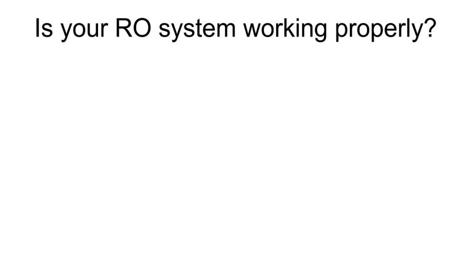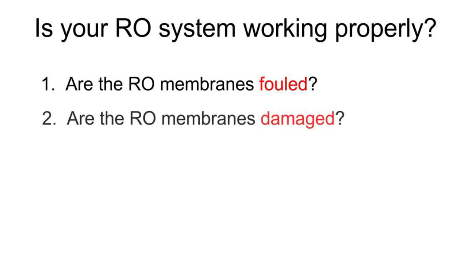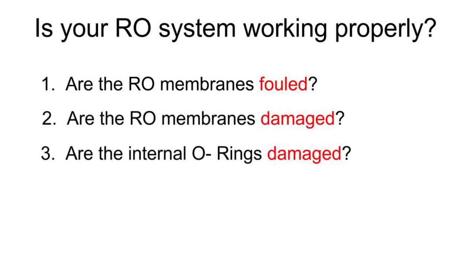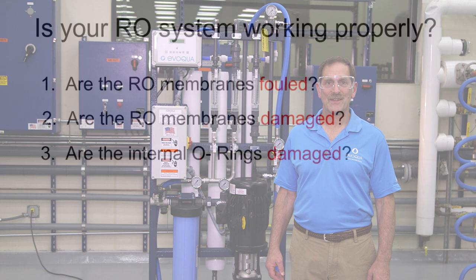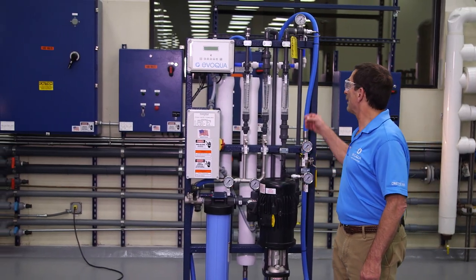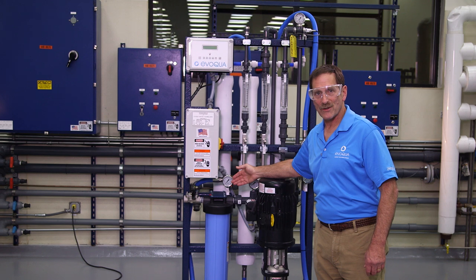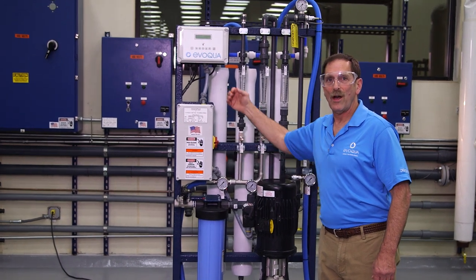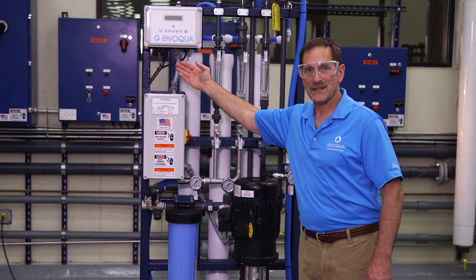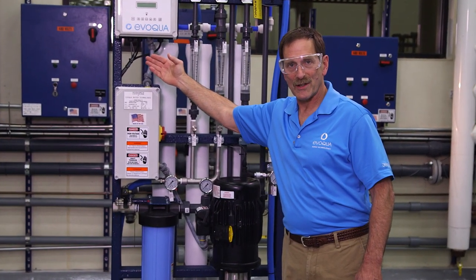You collect data to determine the following: Are the RO membranes fouled? Are the RO membranes damaged? Are the internal O-rings damaged? The data you collect is feed water, product, and reject pressures. Also, feed water conductivity and temperature, and product water conductivity.